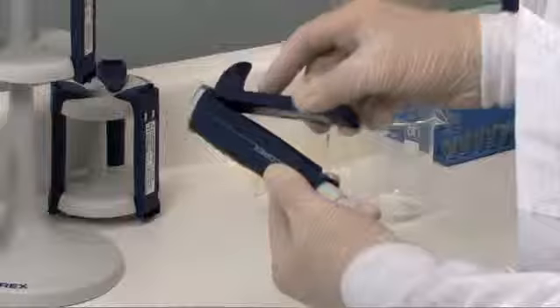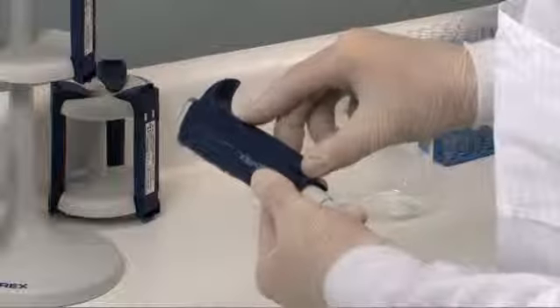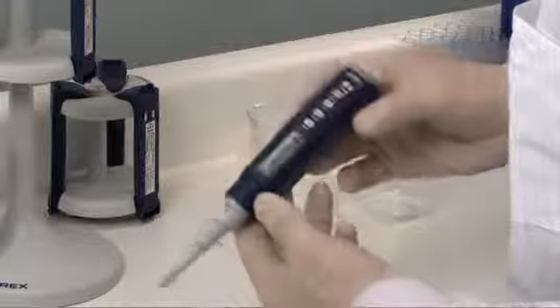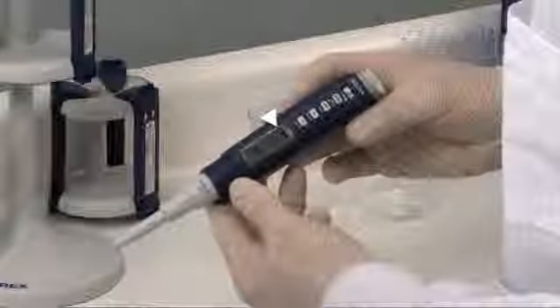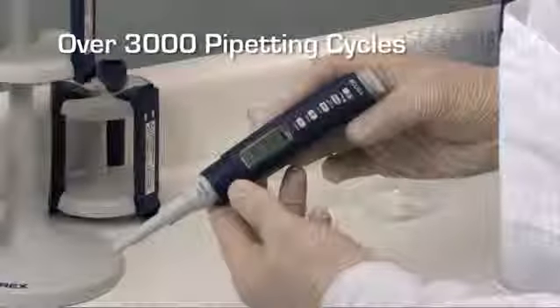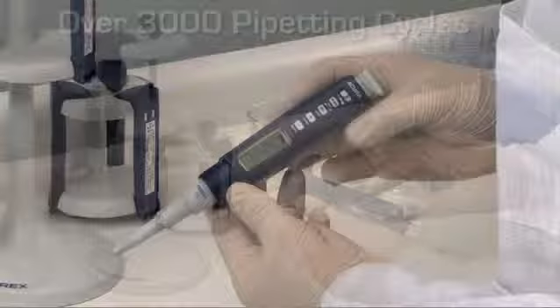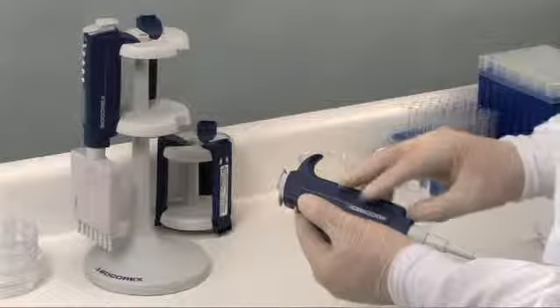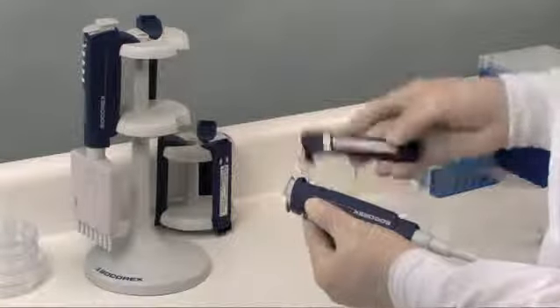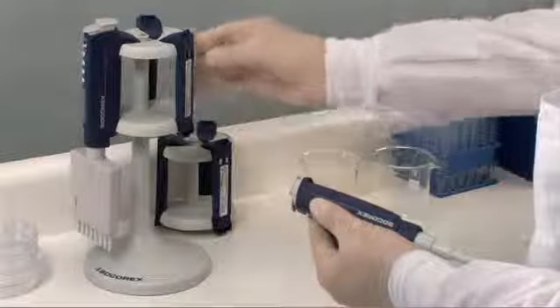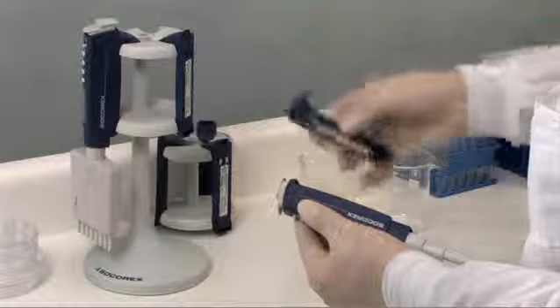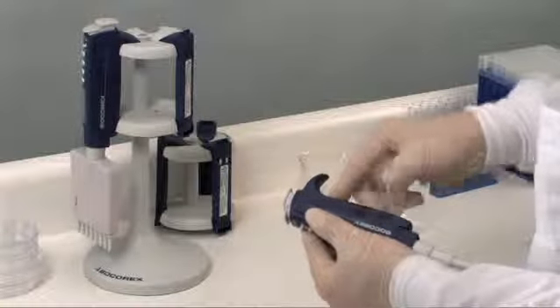The energy source is a rechargeable nickel metal hydride battery. The charging level is indicated on the display. A fully charged battery enables over 3,000 pipetting cycles. Full charging takes about 90 minutes. The battery can be charged while on the pipette or separately on the charging stand. A charged battery is inserted very quickly and easily. Immediately after, the instrument will perform a quick function check.